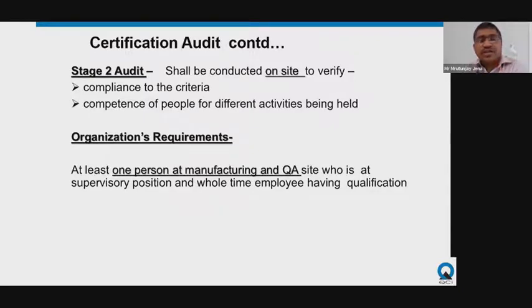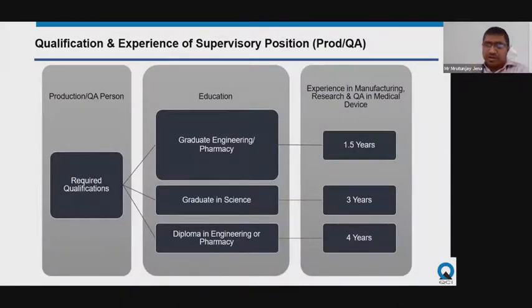So organization requirement, what the industry should have. At least one person on the manufacturing and QA side, at a supervisory position, who is a full-time employee with a qualification. This is the qualification requirement. The medical device manufacturer has to meet this requirement before applying for ICMED level 1 or level 2. So graduate in engineering or pharmacy with 1.5 years experience, graduate in science with 3 years, or diploma in engineering or pharmacy with 4 years experience. There has to be at least one such person in the industry, on the manufacturing side. It should be experience in manufacturing, research, or QA in medical devices.